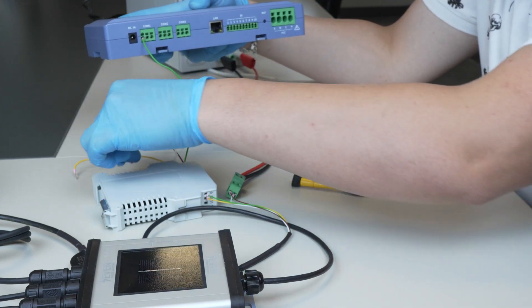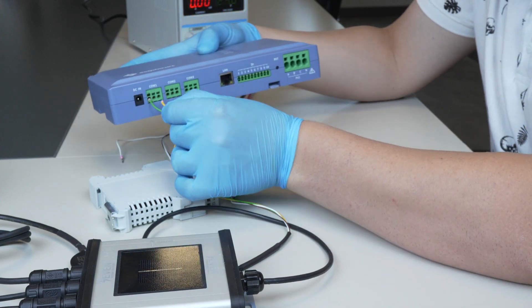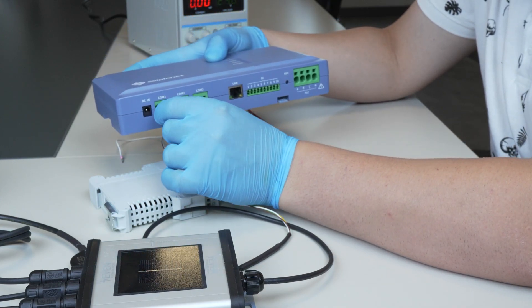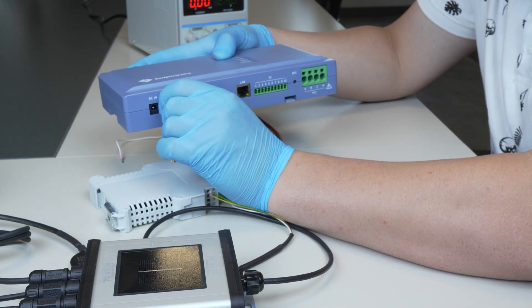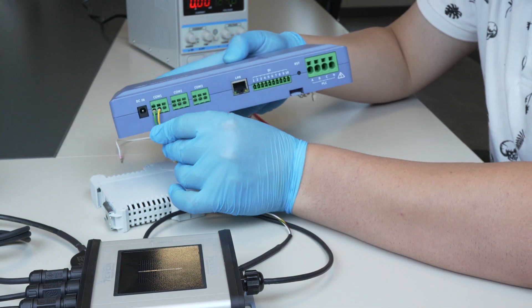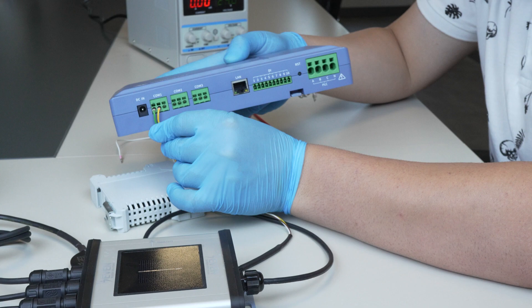The second external cable is connected to the second part of the isolator from one end and the other end of this cable is connected to the COM port RS485B or data minus port on the AI Logger 1000.